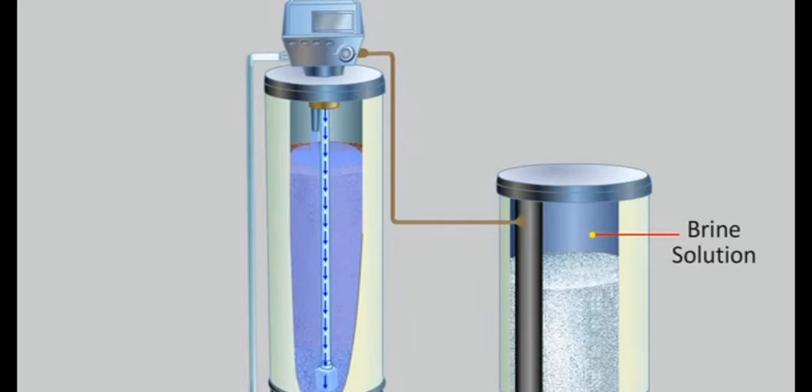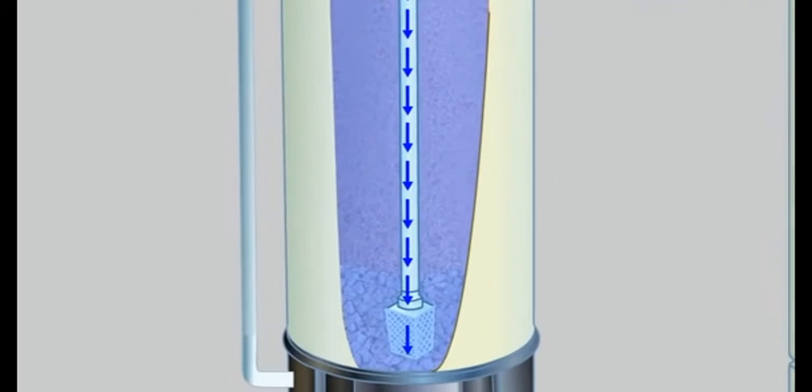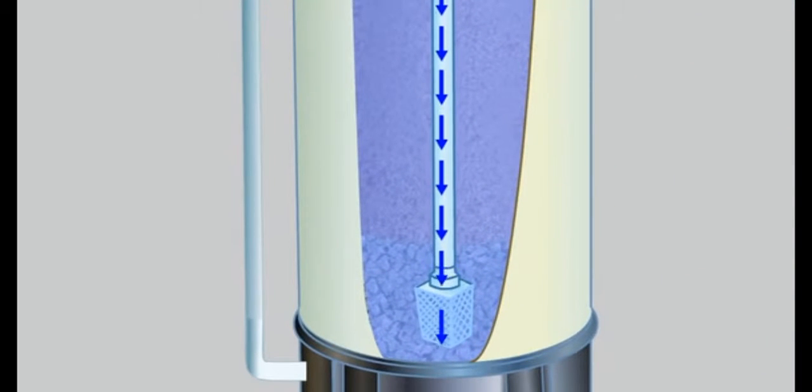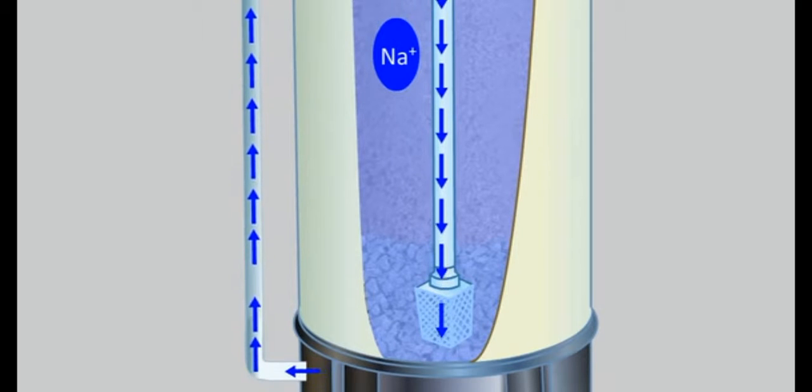Hard water is introduced into the tank from the top. Water reaches the bottom of the tank and then slowly rises through the permutit layer. In the tank, the cations present in hard water are exchanged for sodium ions. The calcium and magnesium ions remain attached to the zeolite and the water becomes soft.